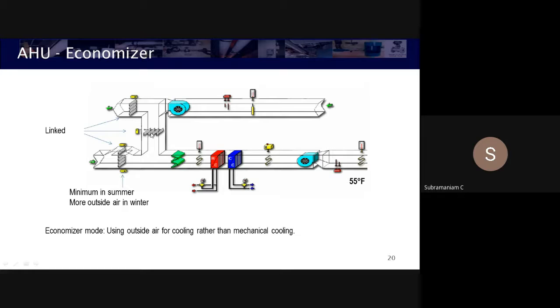Now, for example, in any location, Bangalore or Hyderabad or Madurai or anywhere, during some time of the day your ambient condition may be very amenable. Enthalpy, what we call enthalpy, is heat content. The enthalpy of the ambient air will be less than your room air, which means I can just take my outside air without sending chilled water through the cooling coil.